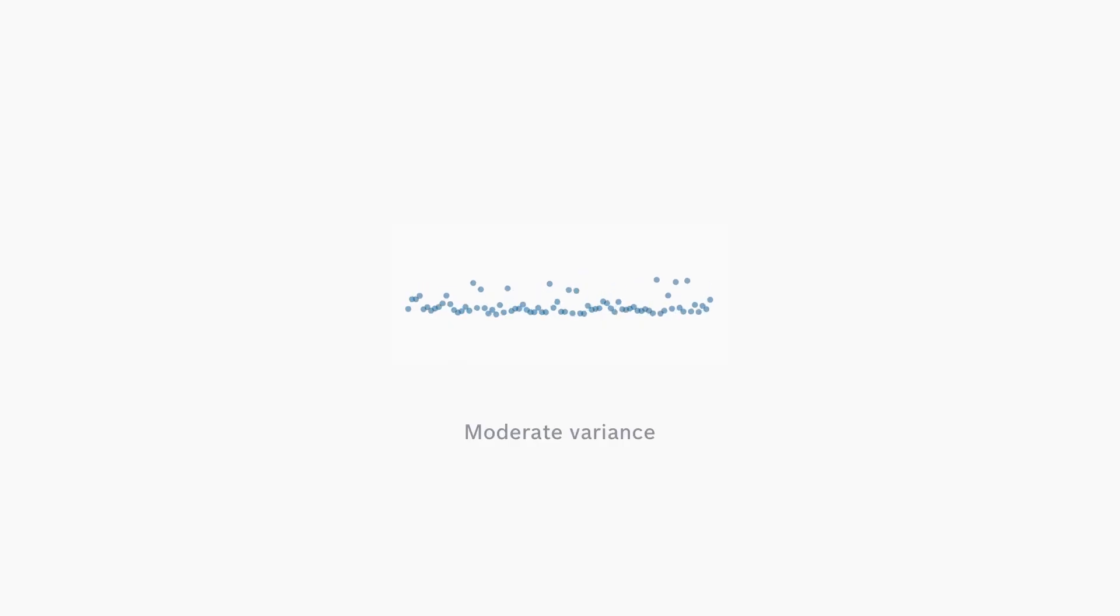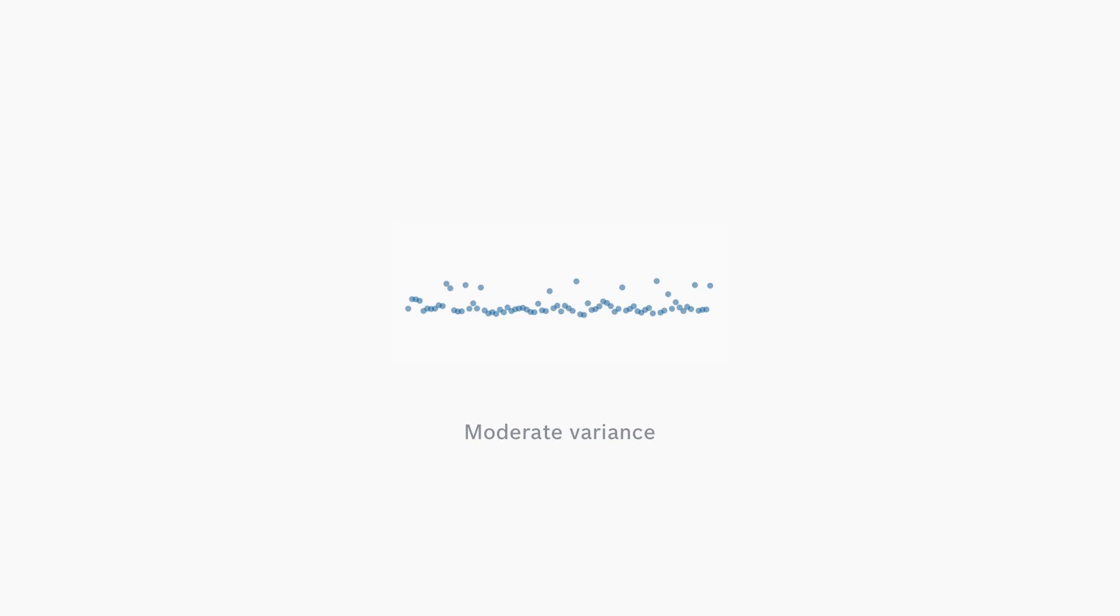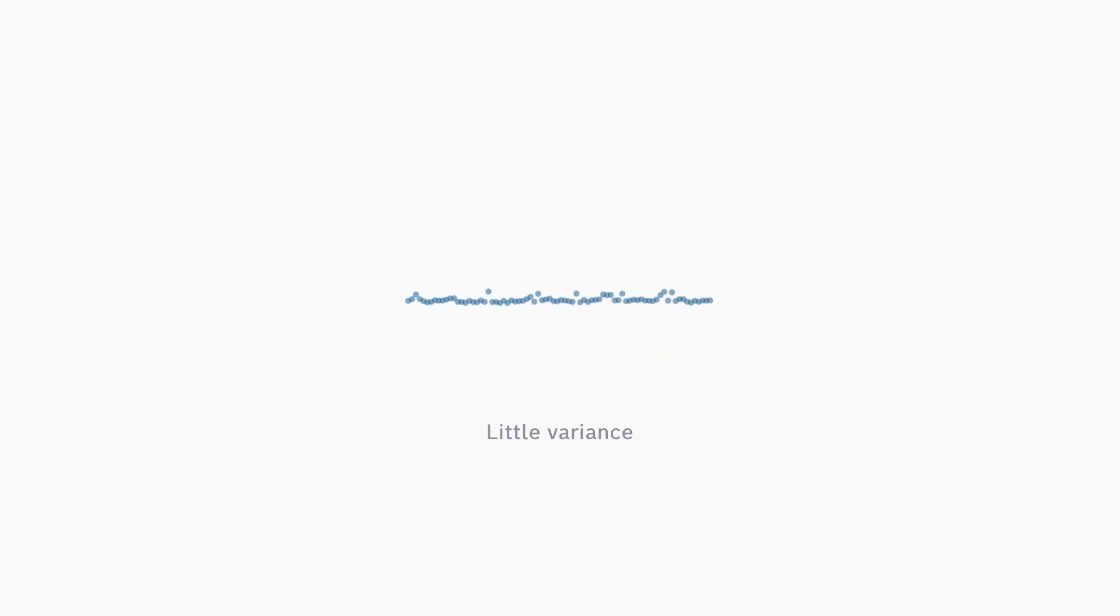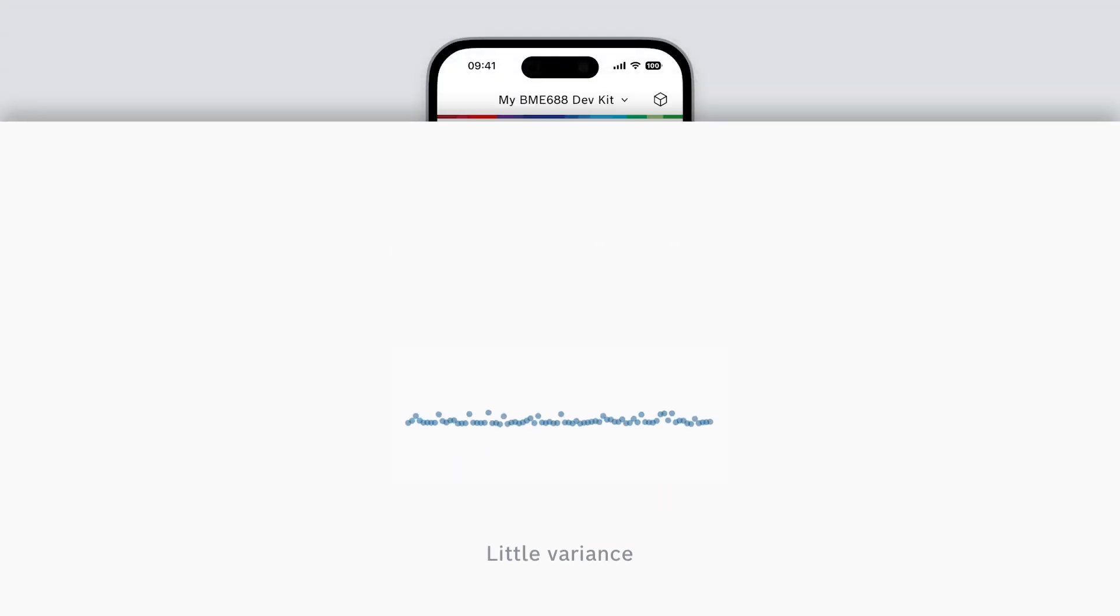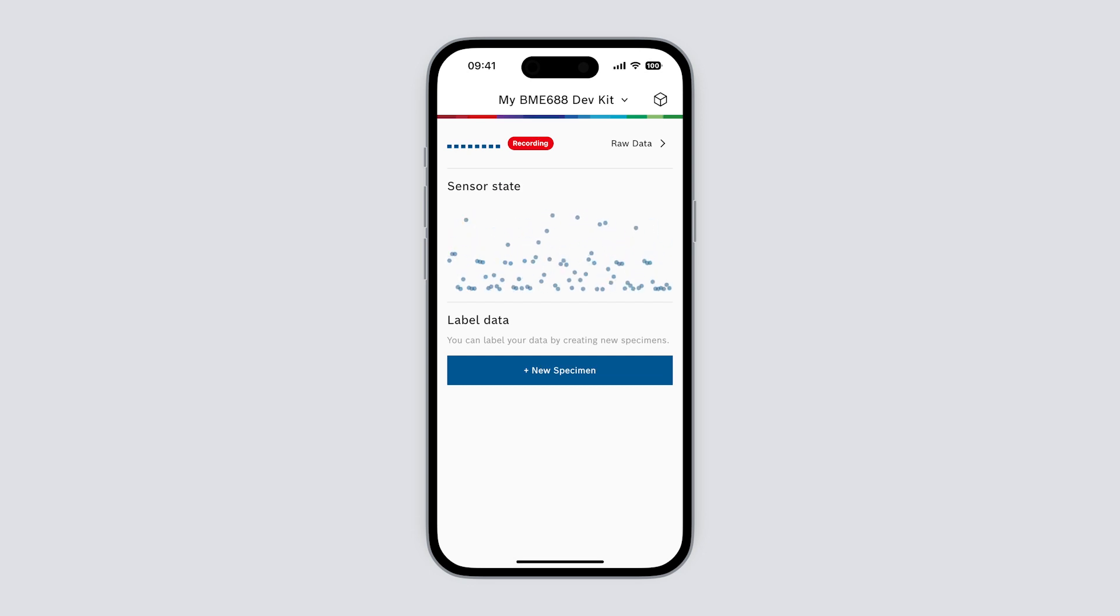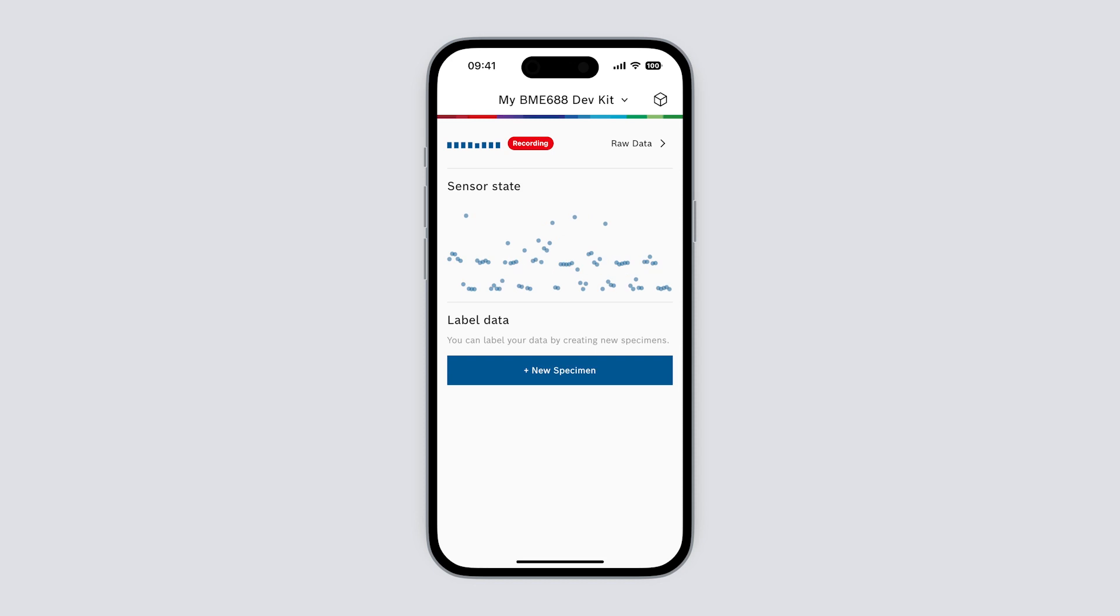The vertical movement of each dot represents the stability or variance of the recorded signal of the respective sensor. The more movement the more variance in the data. The less movement the less variance in the data. The preferred state is the one with the least variance so we want to make sure to wait until the dots have little movement and record that situation.